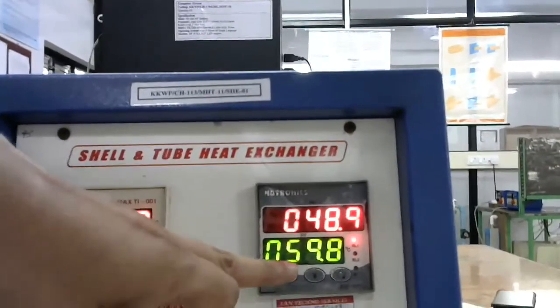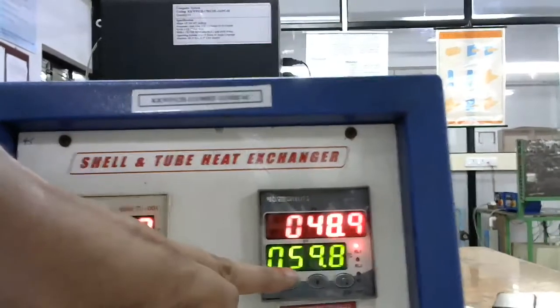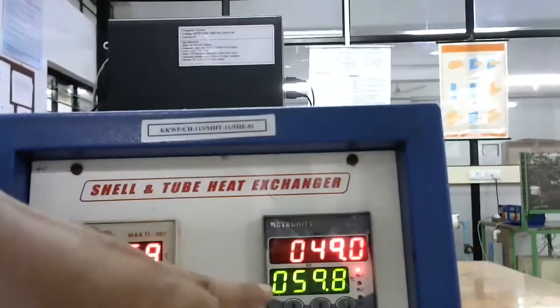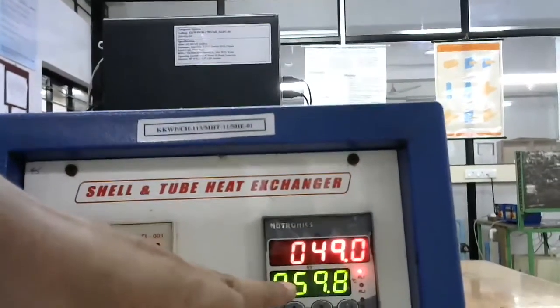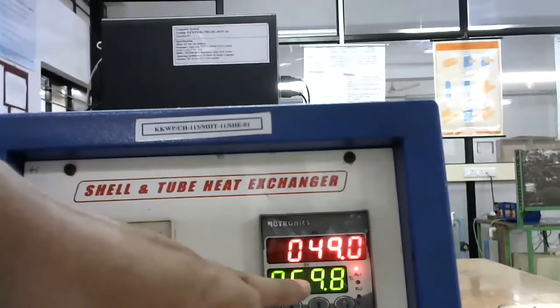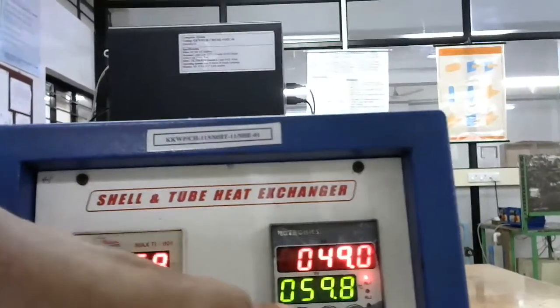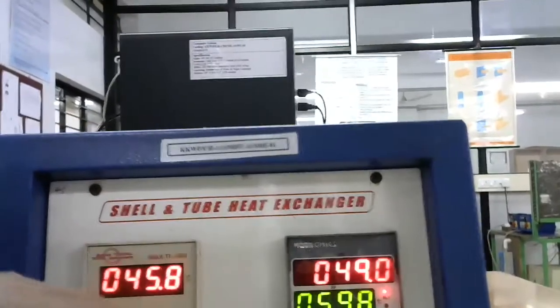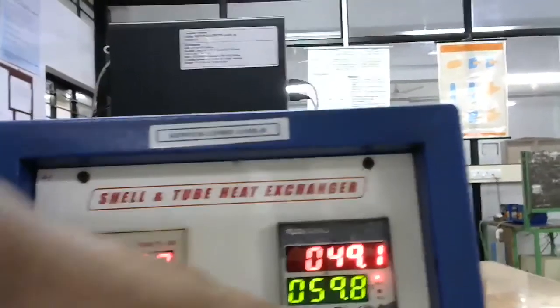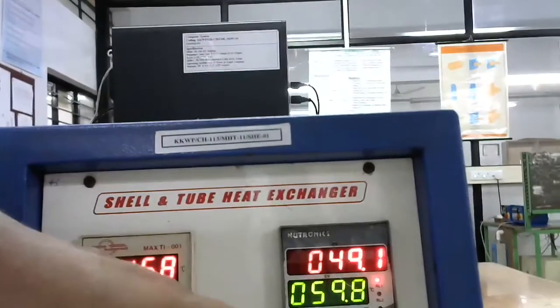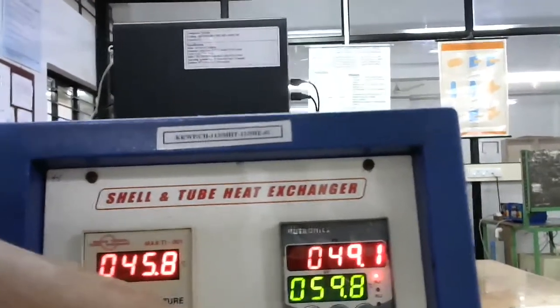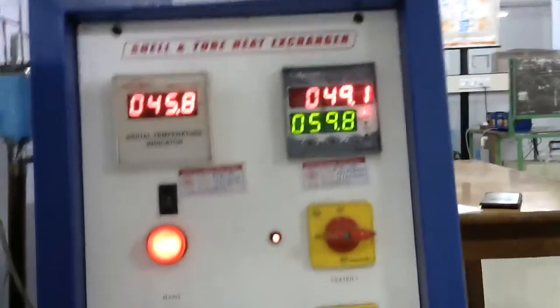So now we have set this as 59.8 degrees Celsius. After the temperature reaches 59.8 degrees Celsius, the heater automatically cuts off and the water again cools. So likewise, we can set the maximum temperature of the hot water in the tank. So this is the arrangement for this shell and tube heat exchanger panel. Now you can understand the actual assembly of this shell and tube heat exchanger.